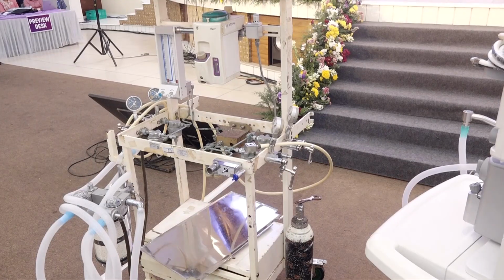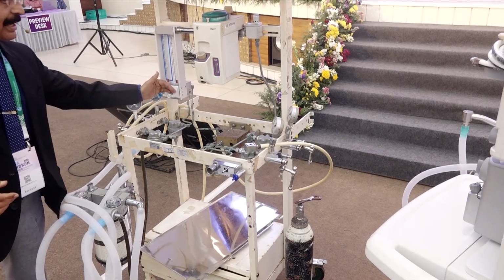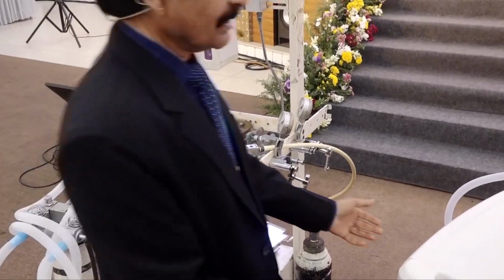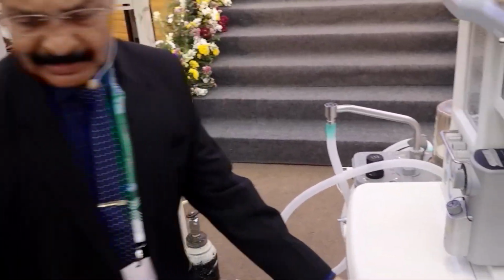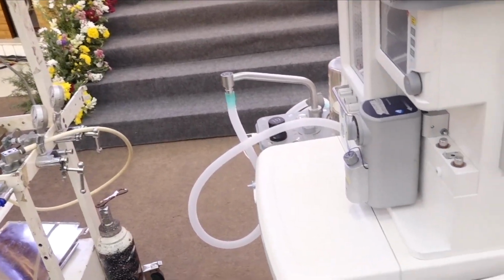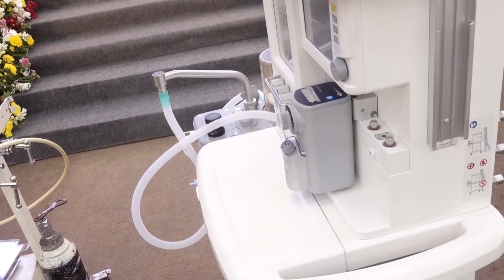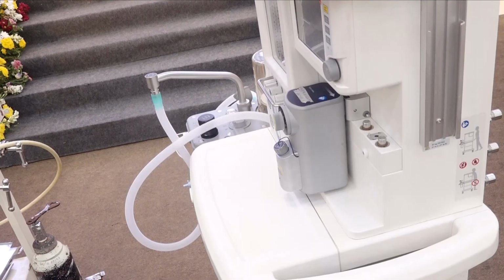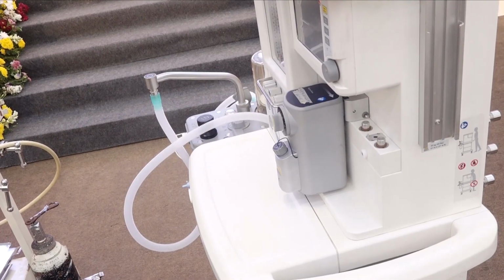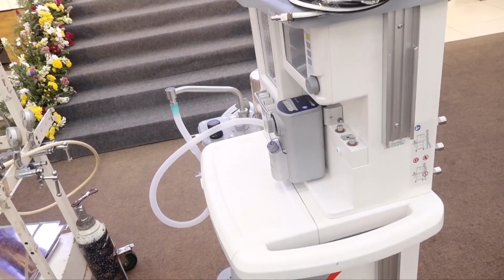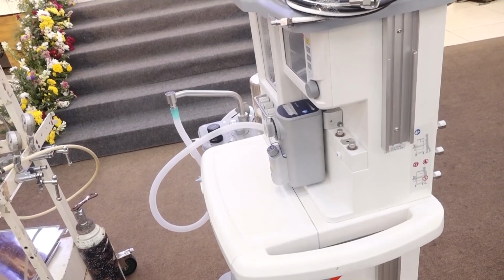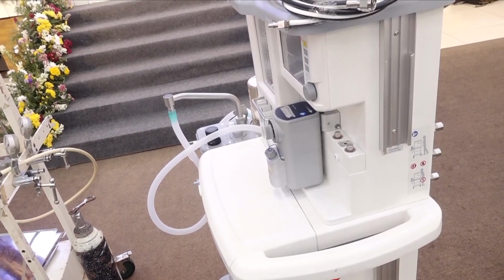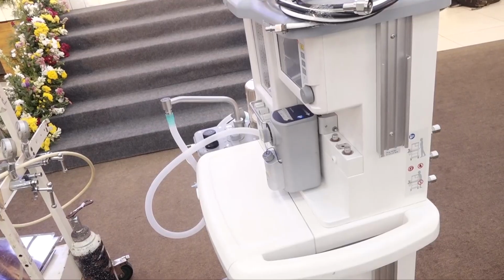And from the flow control valves onwards, what we have is the low pressure system, and at the common gas outlet you have just about 7 or 8 pounds per square inch. So the pressures will continuously come down, and by the time the gases come out, it will be about 8 pounds per square inch. So this is the different classification of high pressure, intermediate pressure and low pressure system.